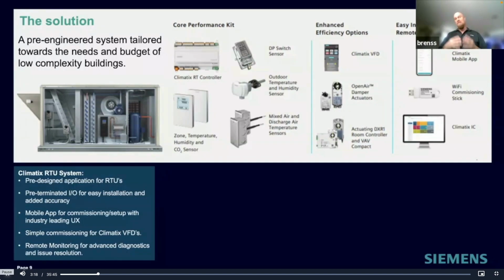There are also a couple of things that we could pair with this to increase the energy efficiency. We have a new Climatix VFD that we could pair with it. That's as simple as one push button to set up. We'll talk about that a little more in a moment. We also have OpenAir actuators, of course, to be used with economization. And now we've introduced, with the DXR, the ability to control multiple zones with the one rooftop, all built into the app. To be able to see these in the long run, the commissioning is all done on a mobile phone. And what technicians don't have a mobile phone on them these days? So everybody always has their unit with them.